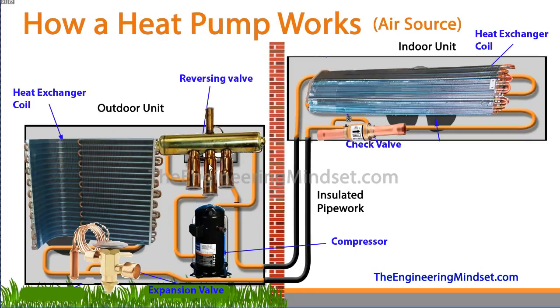Then we've got the reversing valve here, a 4-port reversing valve. We're going to look at in detail how this works in another video. Then we've got the outdoor heat exchanger coil, and as mentioned we've also got the expansion valve here, which is a thermal expansion valve with a capillary tube attached to that. Now this is just an example of how the real world components might look. It could be a slightly different setup, but this is just to help you understand how the system works.